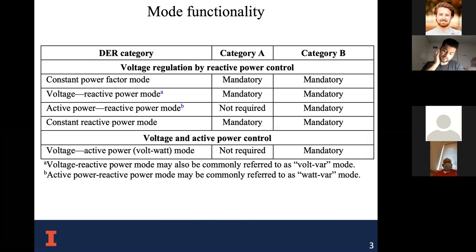But before I talk about the use cases and attacks, just an overview of the different kinds of modes, so that we can understand the standard better in terms of reactive power and active power modes. With the reactive power modes, there are four options. The first option is constant power factor mode, which is basically constant power factor, as the name says. The second one is voltage-reactive power mode, which is the same as a volt-var curve. The third is active power-reactive power mode, where based on your active power, you give a certain reactive power value. And the fourth one is constant reactive power, which is just a basic constant value of reactive injection or absorption. And then for the active power control mode, there's only one mode, which is voltage-active power, which is basically going to give your watt value based on your voltage level.